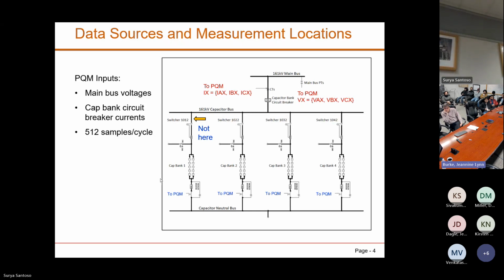Our power quality monitor is actually located right here - the voltage is measured at the main bus, and the current is measured at the capacitor bank circuit breaker. So our data source is not coming from the ideal location - if we had the power quality monitor located elsewhere, it would be much easier to develop our machine learning models. Instead, our power quality monitor is here, so the current measured here will see all the currents together.